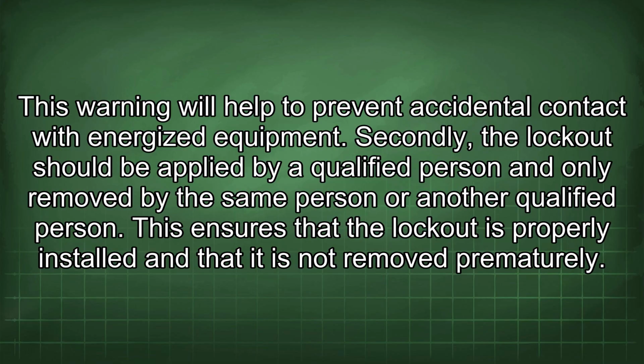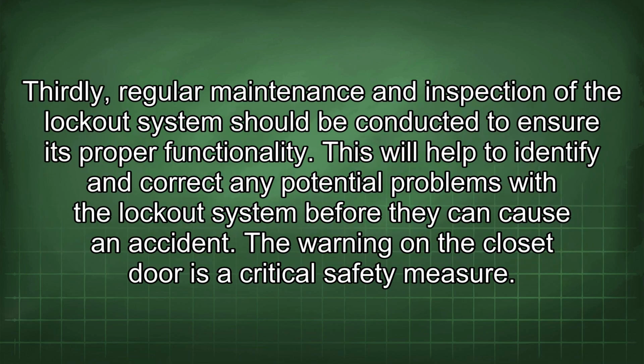Secondly, the lockout should be applied by a qualified person and only removed by the same person or another qualified person. This ensures that the lockout is properly installed and that it is not removed prematurely. Thirdly, regular maintenance and inspection of the lockout system should be conducted to ensure its proper functionality.